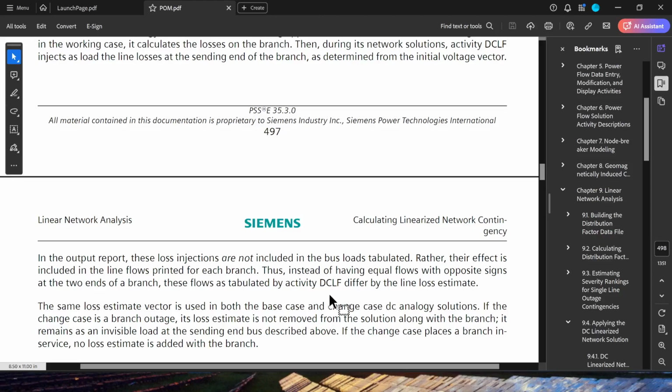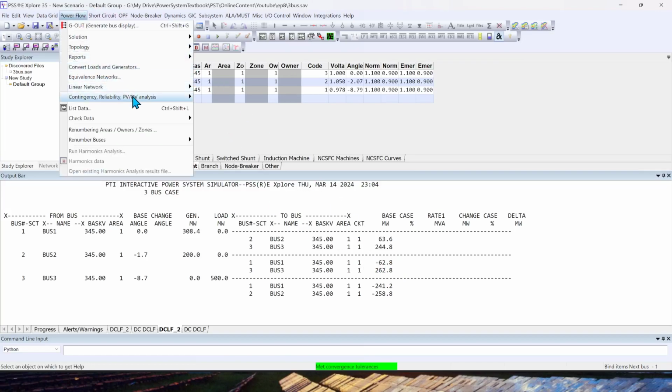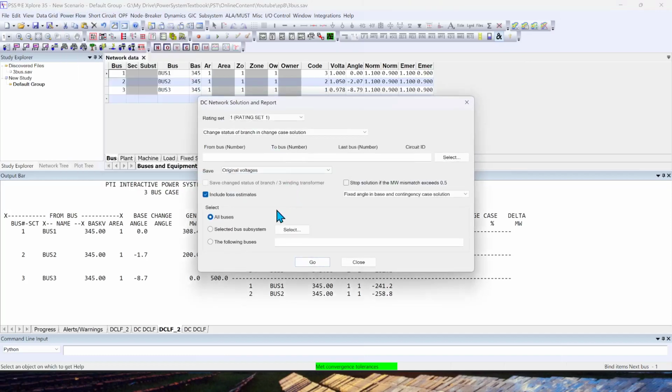On further investigation, I also found that if you are using an older version of PSSE, which is version 33, the default is that the line losses are modeled and there is no option to ignore them. The option to ignore line losses in the DC load flow was added from version 34.